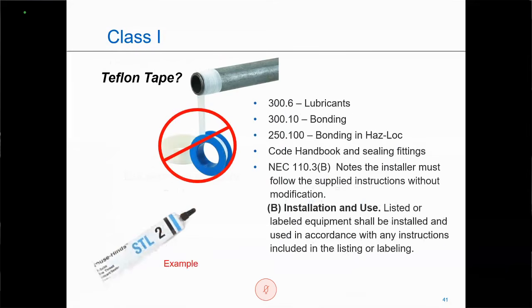Now, when we're working with our conduit, there are times that you're going to want to make sure that it threads easy enough, or if you have junction boxes with threads, you're going to want to have some assistance in threading, especially if it's copper-free aluminum, because you can have the threads bind up on you. But what you cannot use is plumber's Teflon tape. Manufacturers do have products that are approved for use with their particular equipment, in which these have been tested. Typically, these products are non-petroleum based, so they're going to maintain your bonding and grounding, but they're also not going to be a possible ignition source.